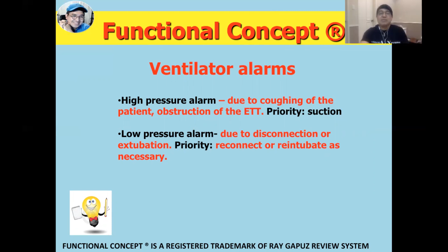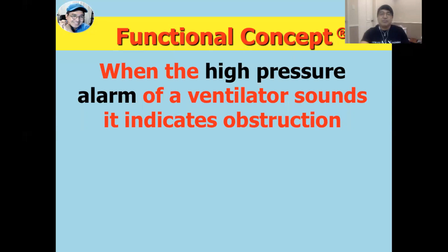Okay, so if there's an obstruction of the tube of the patient, it's going to be the high pressure alarm that sounds. If there's going to be extubation, it's going to be the low pressure alarm that sounds. So when the high pressure alarm of a ventilator sounds, it indicates obstruction. When the low pressure alarm of the ventilator sounds, it indicates disconnection or air leak.